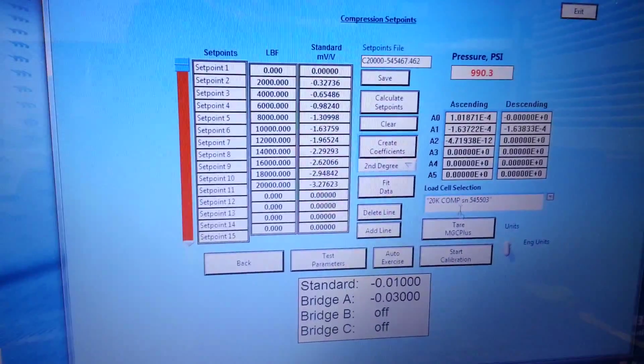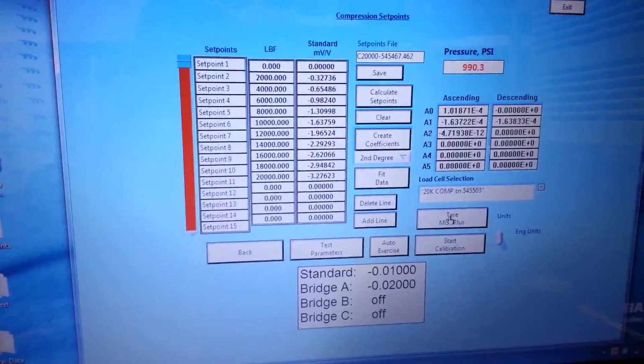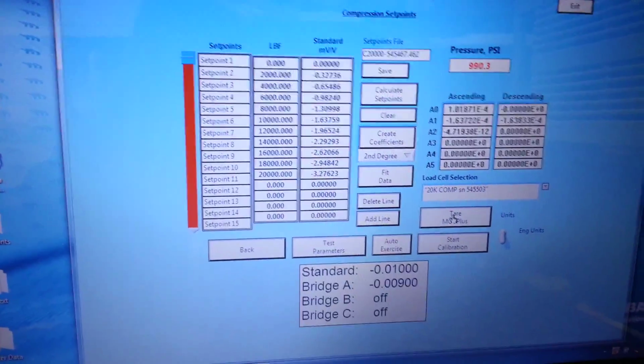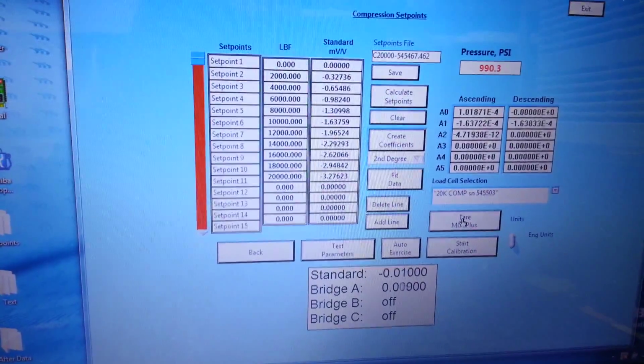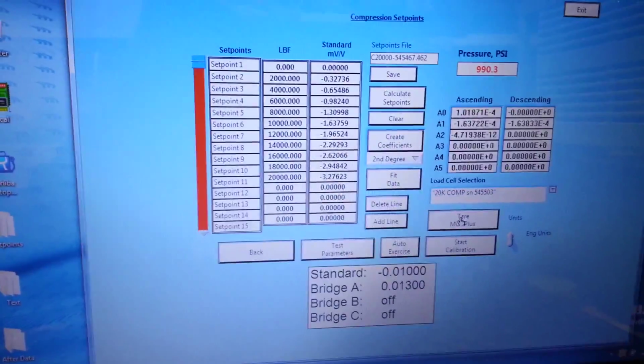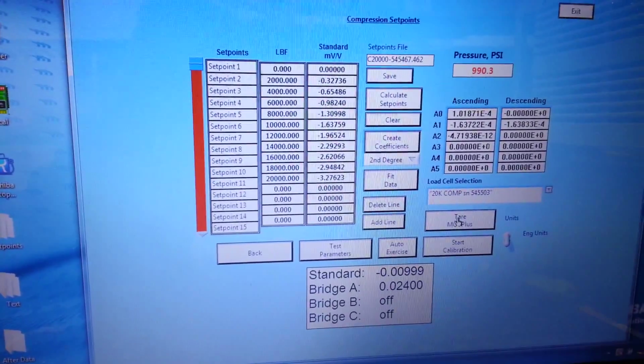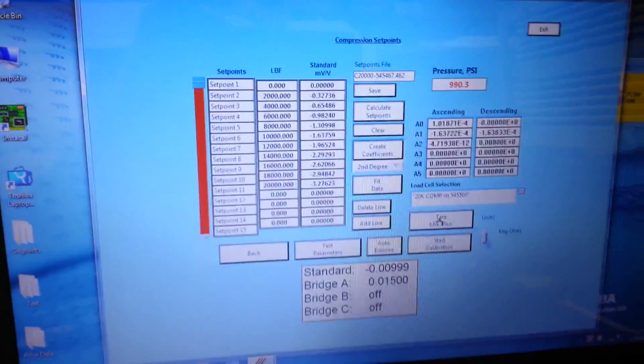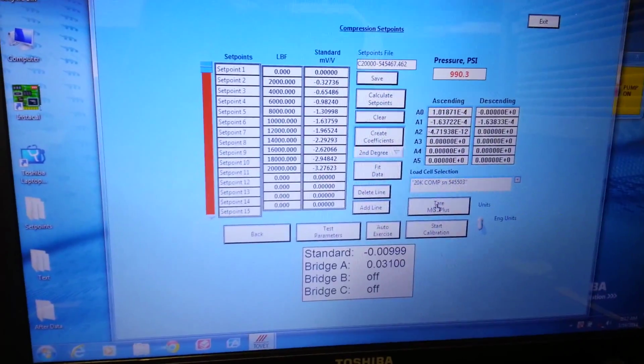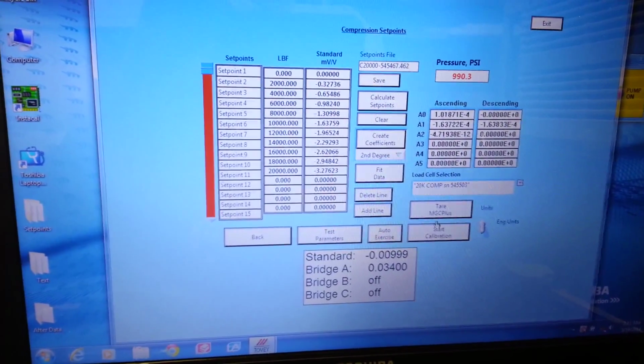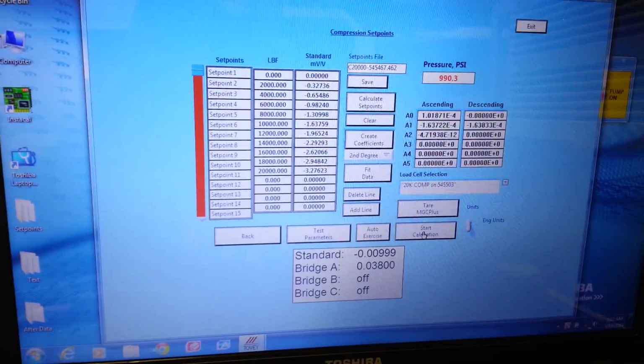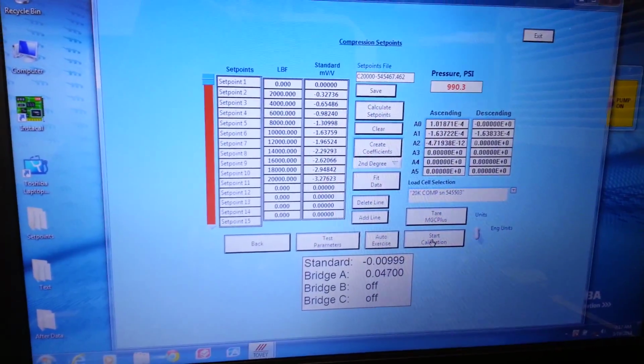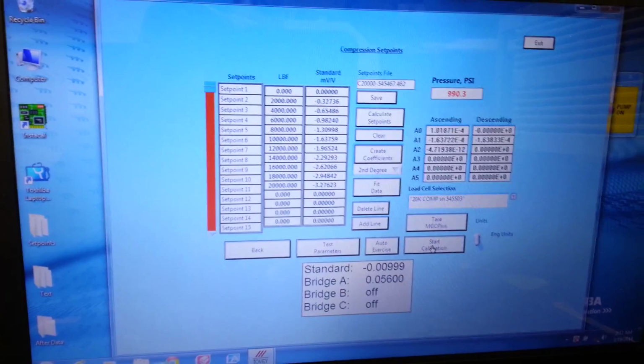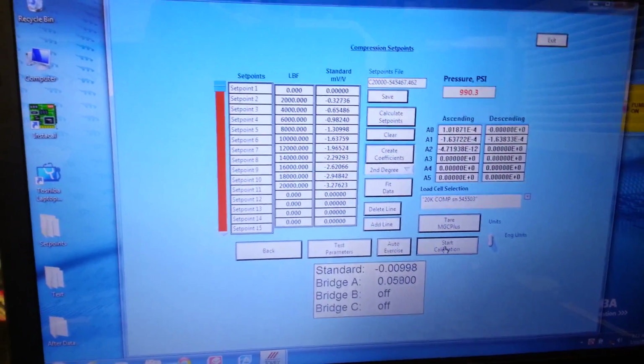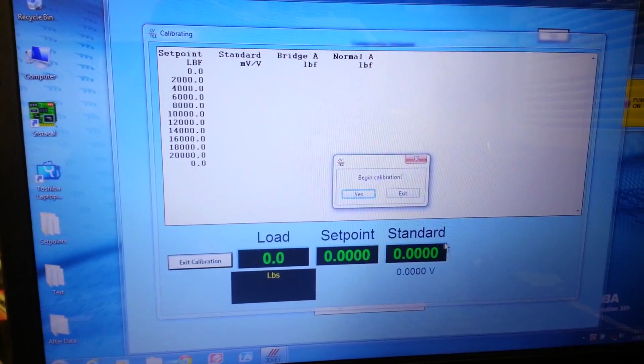So what I'm going to do now is tare the MGC Plus to have a better zero, and then I am going to start the calibration. This is at 0 degrees, so no plates are underneath the load cell, and you can see how fast and how efficient this machine works when all the bugs are worked out of it. Let's go ahead and start calibration. Begin calibration, yes.